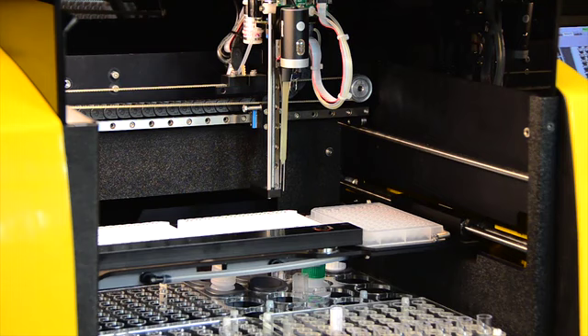There are many other systems on the market. They have a single probe liquid handling system, but then a full strip washer. However, in a situation like that, you're never going to get the timing exactly correct. Therefore, a 30-minute conjugate incubation, then a wash, then a dispense of a substrate is always going to be off by a little bit because assumptions and estimations need to be made. With our system, every single well will be treated identically. So if it takes 10 minutes to process the washing step, every well will sit for 10 minutes. If it takes a half an hour for a conjugate incubation, every well will sit for exactly 30 minutes. To us, we believe that this is the correct way to be processing ELISAs.